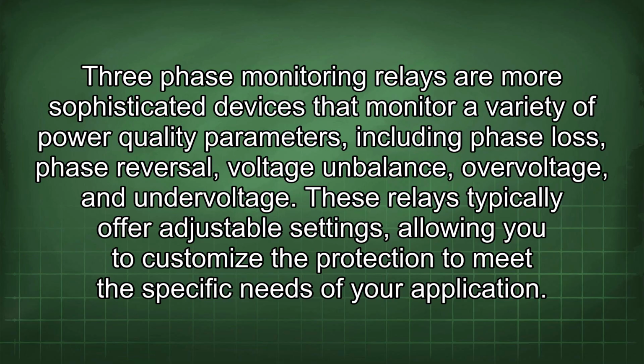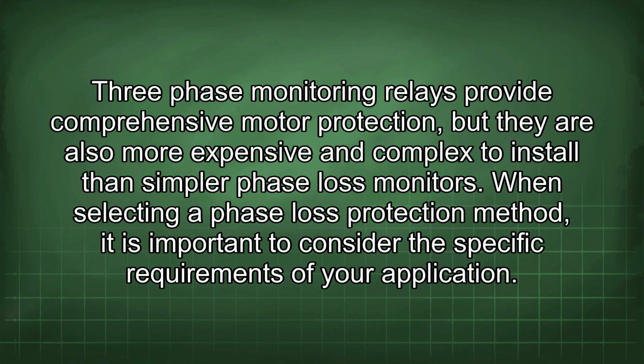Three-phase monitoring relays are more sophisticated devices that monitor a variety of power quality parameters, including phase loss, phase reversal, voltage imbalance, overvoltage, and undervoltage. These relays typically offer adjustable settings, allowing you to customize the protection to meet the specific needs of your application. Three-phase monitoring relays provide comprehensive motor protection, but they are also more expensive and complex to install than simpler phase loss monitors. When selecting a phase loss protection method, it is important to consider the specific requirements of your application.